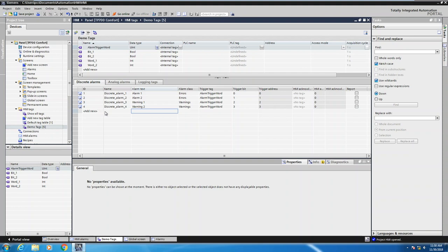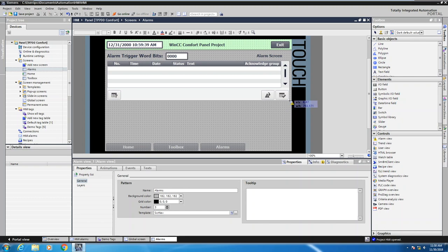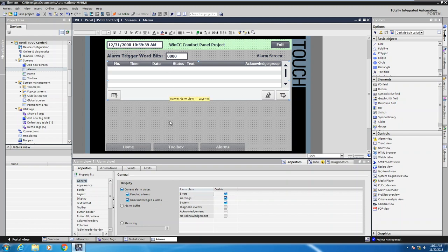Next, I'm going to move over to my screens and open up my alarm screen. This is where I'll present my alarm conditions to the operator. In my toolbox, I'll select Controls and find the tool called Alarm View. I'm going to draw an alarm view out onto the screen. There's a toolbar across the bottom with some buttons available, including an acknowledgement button on the far right which we can use to acknowledge our alarms. When we drop the alarm view on the screen and look at the general properties under Display, it is set up to display the current alarm state, so any new alarm conditions will show up in this window during runtime. Within the current alarm window, you get one line per alarm showing the most recent state of that alarm.